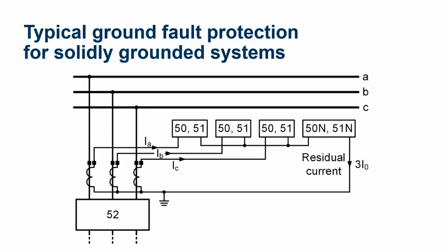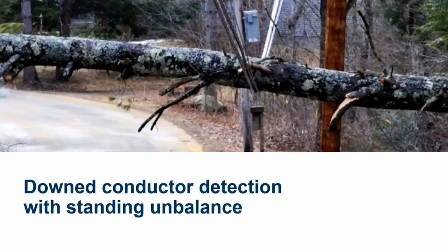So I need another method specifically to detect high impedance faults on the power system, because in many cases, especially on 4-wire multi-point grounded systems, whatever our standing imbalance is, or the worst case standing imbalance, dictates the sensitivity of our ground fault pickup. For traditional protection, we have to make sure we set it above that so that we don't have a nuisance trip. So how can we detect these?